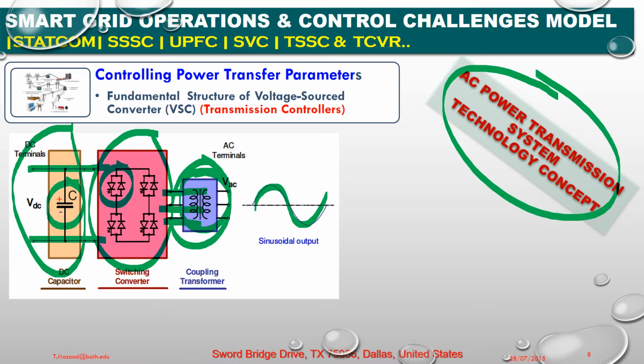AC filters may be necessary, and the series inductive interface limits the consequent current harmonics entering the AC system side. Basically, a voltage source converter generates AC voltage from a DC voltage. This is the DC voltage, and over here the AC voltage is generated, often referred to as an inverter. It has the capability to transfer power in either direction.